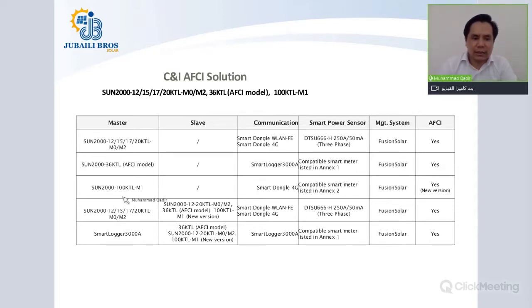Monitoring platform is FusionSolar. Scenario 3, if you need AFCI, you can again have the Sun 2000 100KTL-M1, and you have the option of using a smart dongle 4G. Not limited to the 4G dongle in this scenario, you can also use a smart logger, but that is classified as the fifth case here in this table, which I will be discussing as well. Number 4, you have the option of using Sun 2000 12 to 20 KTL, but also with a slave inverter. The slave inverter could be any other 12 to 20 kilowatt size, a 36 kilowatt inverter with AFCI model, or a 100 kilowatt size inverter. Communication in this scenario can happen through WLAN-FE or a 4G dongle, alternatively a smart logger as well. Power sensor you can use from Huawei itself or even from a third party. Management system you can use from FusionSolar.